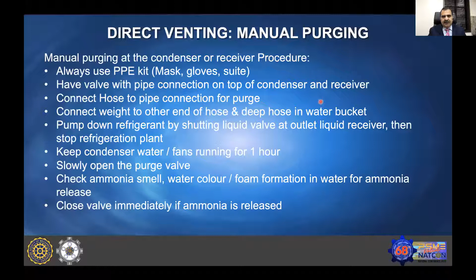So this is a very risky and tedious process, particularly if your condensers are installed above the plant or on the terrace. It is very difficult to operate those. So we recommend do not try manual purging without proper precautions. It happens that because of this, operators do not do it regularly, and the frequency is very low. It takes a lot of time, needs the plant to be shut down, and total air removal is not possible.